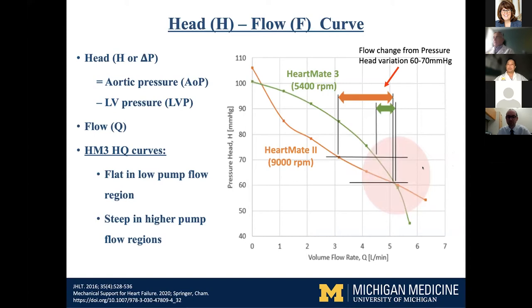About the pump mechanics — it's a busy figure, but the HQ curve is important to discuss because it relates to subsequent issues we face working the HeartMate 3 pump and adjusting speed. There is what we call a head pressure — basically the pressure across the pump — which is aortic pressure minus LV pressure. That's the head pressure. Then there's flow, which is Q.